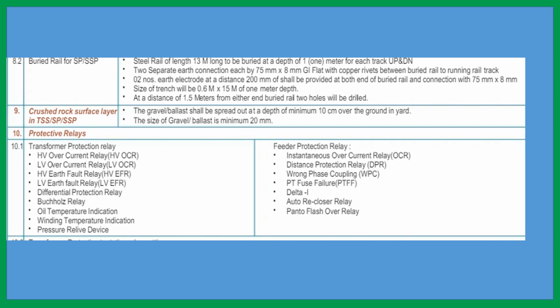Then feeder protection relay, instantaneous overcurrent relay. Already I have told distance protection relay. Distance protection relay, that means when the OHE grounds, creating an earth fault but away from the TSS, and the current is not sufficient to trip the overcurrent relay, or it fails to trip the overcurrent relay, or maybe the overcurrent relay and distance protection relay may come at a time.